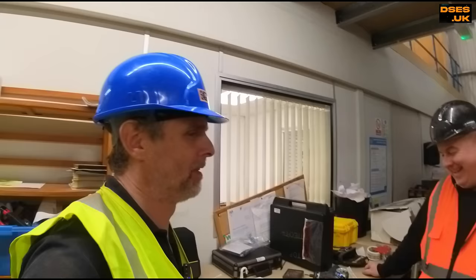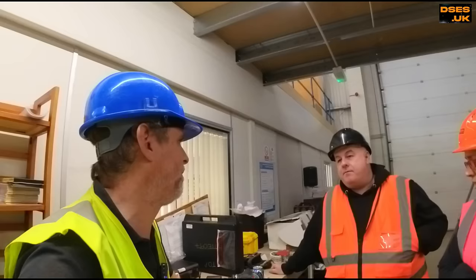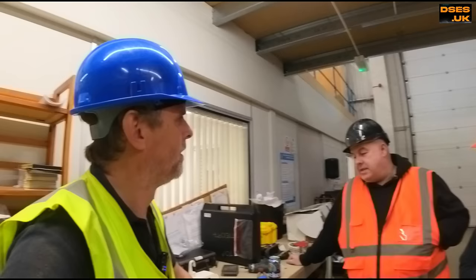Not really any electrical testing to do, because we haven't done any kind of modification on the fixed wiring. So, you know, we've verified. Loop tested the socket. Yeah, it's been loop tested. Do we have to start pulling the board apart to get a Ze for the minor works, or a Zs at the DB at least, or any insulation resistance? Do we bollocks? It's just the light we're plugging in. Exactly. So, yeah, easy work.